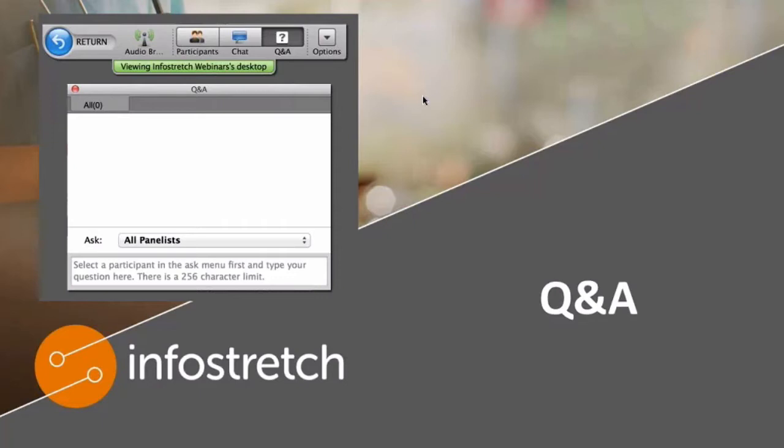But if we go into the integrity of these terms in the compliance industry, verification is testing and confirming that the output of the software in a particular phase of your project development lifecycle is as intended and desired. Validation checks whether the final software is what was expected in the requirement phase. So the main difference is that verification looks for intermediate checking of the software, whereas validation confirms the final software product.